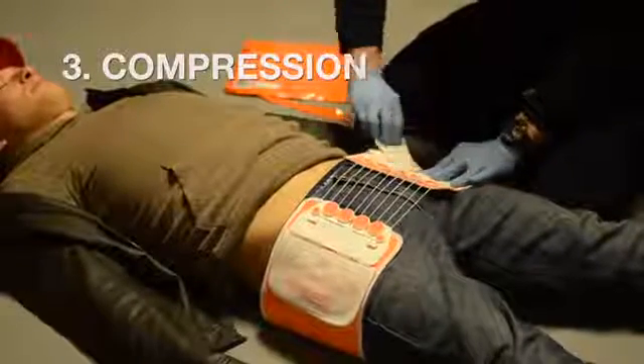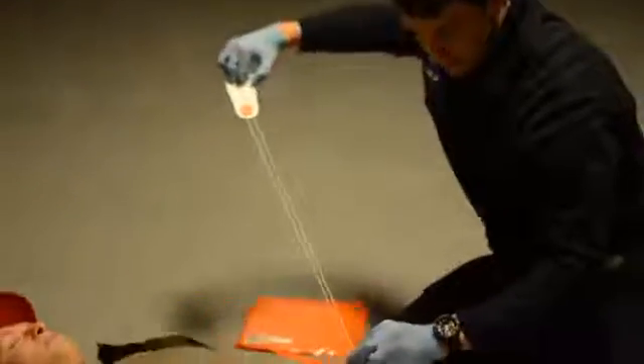Pull the pull tab toward you. Use even pulling force. Use your non-dominant hand to guide and monitor the application of the circumferential pressure. When the pulley system has closed the 6 to 8 inch gap, or if you feel the pelvis is stabilized, then begin the next step.